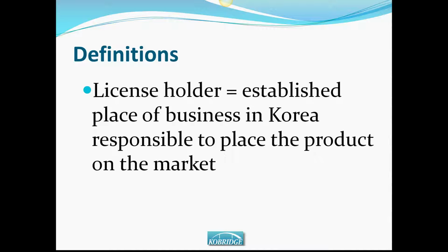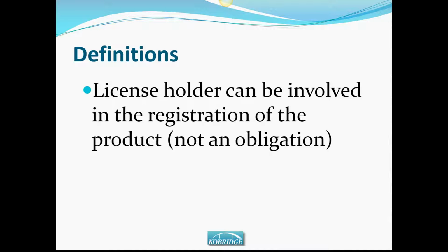So the license holder is an established place of business in Korea responsible to place the product on the market. It can be involved in the registration of the product, even though that's not always the case. The registration itself can be done by a consultant or even by the distributor.